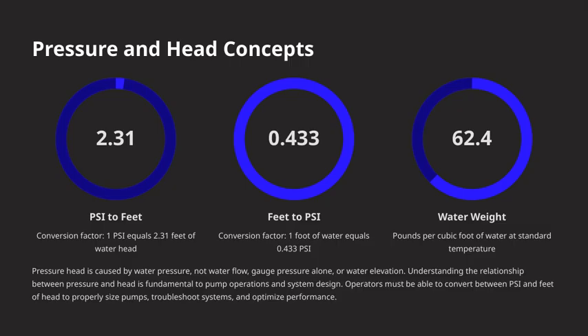Conversely, if we know the head in feet, we can convert that back to psi by using the factor 0.433. It's also important to remember that water weighs about 62.4 pounds per cubic foot at standard temperature. That weight influences how pressure and head relate to each other. Now, when we talk about pressure head, it's caused by water pressure itself, not by the flow of water, gauge pressure alone, or simply the water's elevation. This distinction is essential because understanding the relationship between pressure and head is fundamental to pump operations and system design.